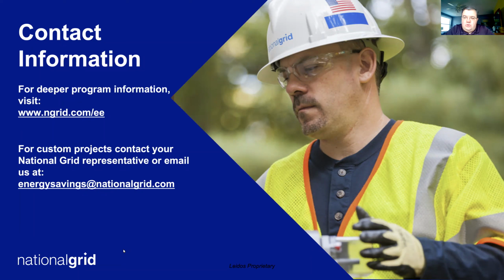So what I like about the wireless sensor market is the real takeaway is most folks have some sort of boiler reset control already, and that boiler reset's responding to outdoor air, return water, or condensate return temperatures, and making some determinations for that. But it never knows what's going on truly within the space itself. When you add these wireless sensors into the space, into the hallways, the apartments, whatever that is, you're giving another level of feedback to the controller so it can make better intuitive or iterative adjustments to the boiler operation. So it's a relatively inexpensive solution with great benefit and quick payback.